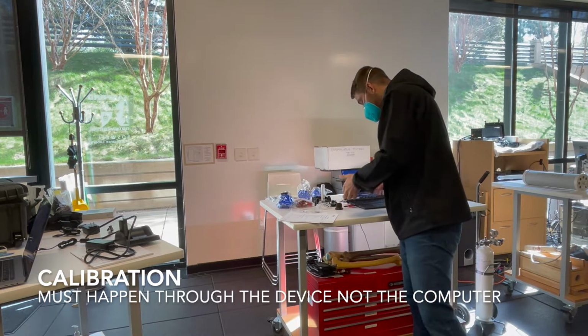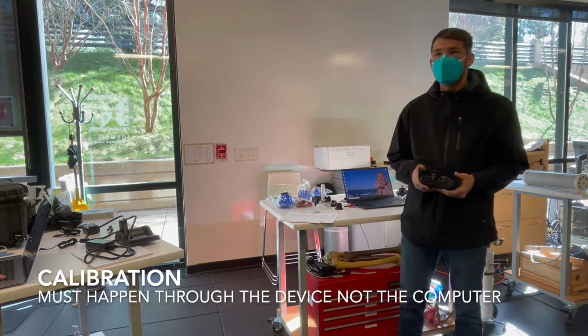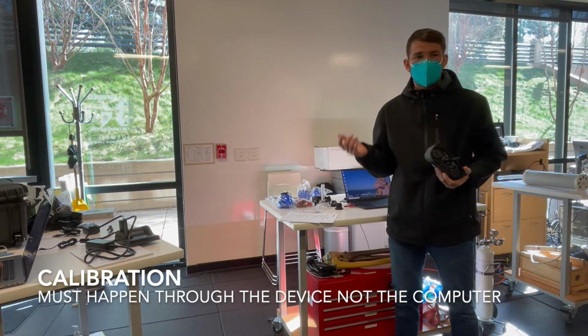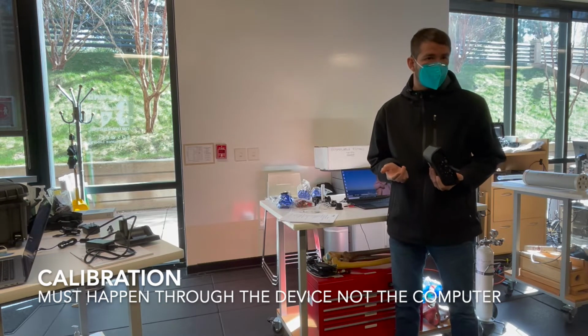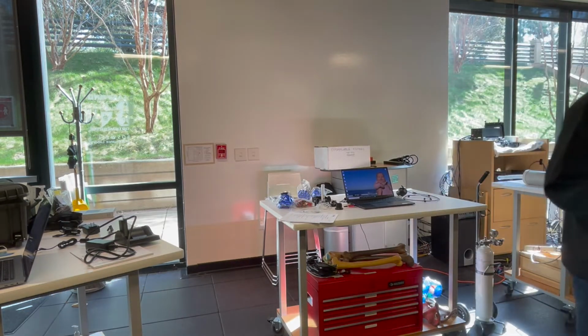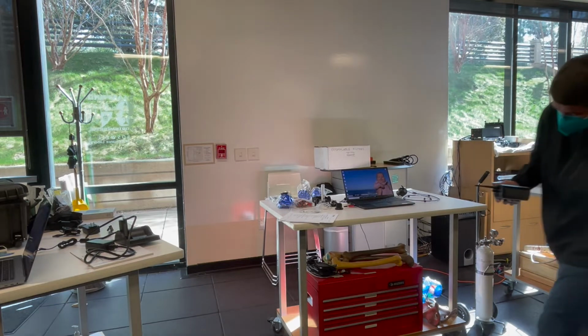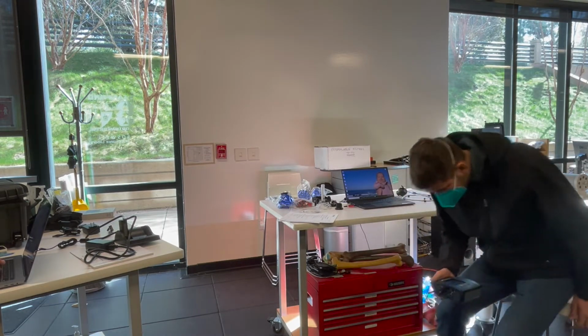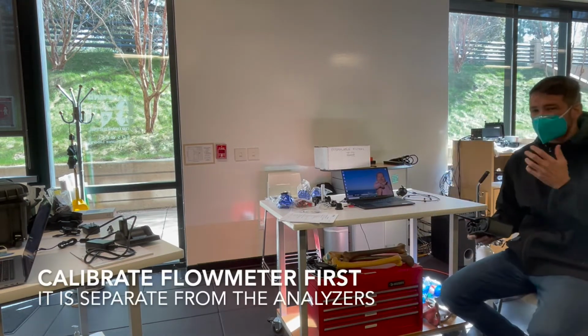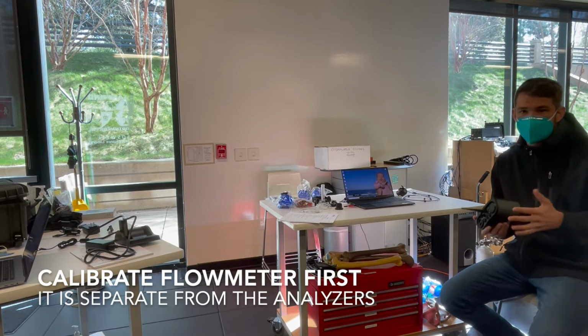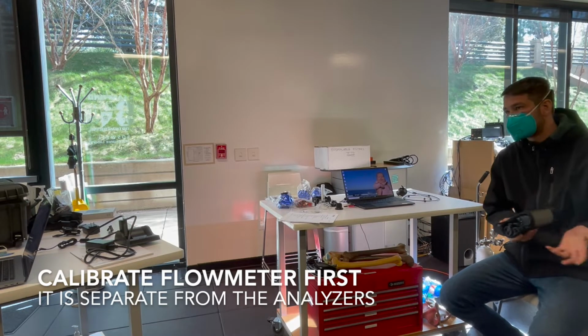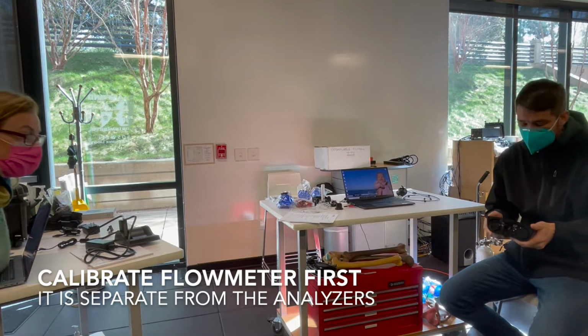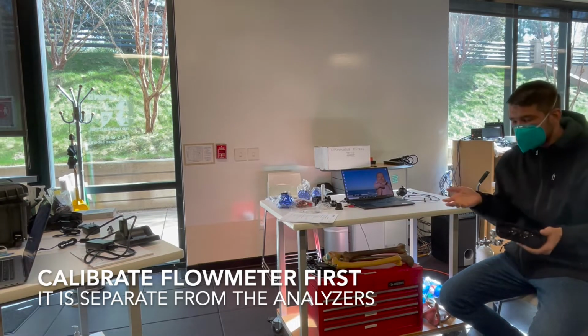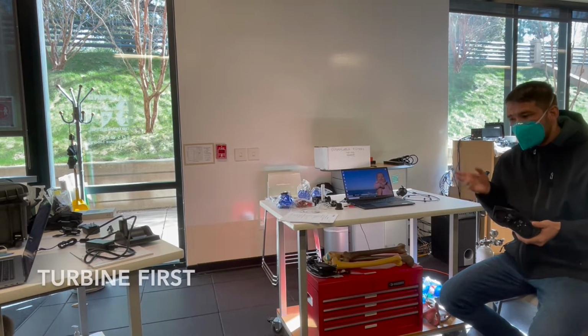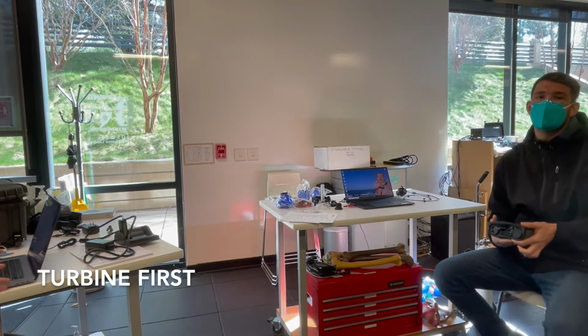So if we're going to be testing inside, there's going to be more calibrations that need to be done than if we were only testing outside. And so what that looks like is you're always going to calibrate the flow meter first, just because it's separate from the analyzers. It doesn't have anything to do with the analyzers. So you'll calibrate the turbine first, and then if you're testing indoors, you're going to want to run what's called a CO2 scrubber.